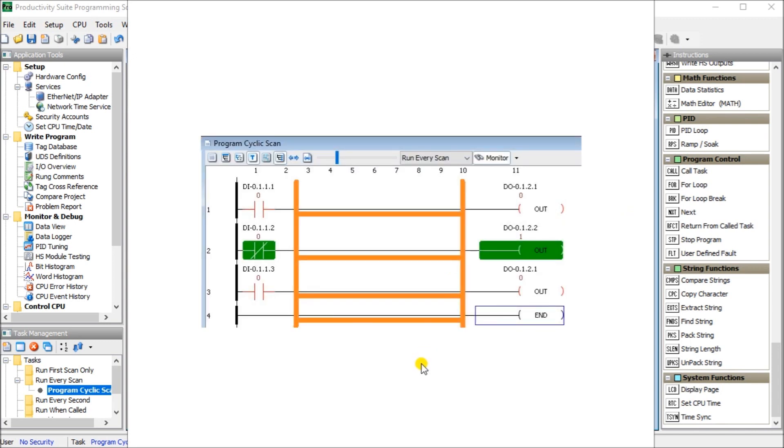Ladder logic is the most common method for programming of PLC. The graphical language comprises of a series of rungs. They form to look like a ladder. Inputs are on the left side of the rung and outputs are on the right side. If an input condition or conditions are true, then the outputs of the rung are true. If the input logic is false, then the outputs will be false.